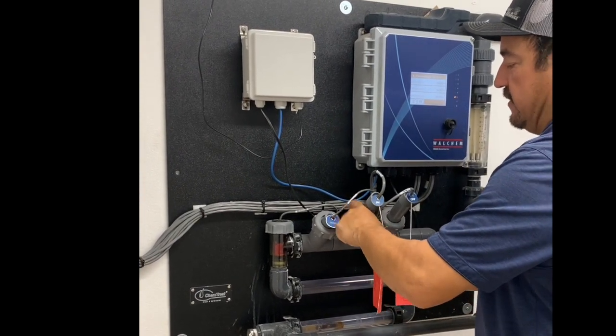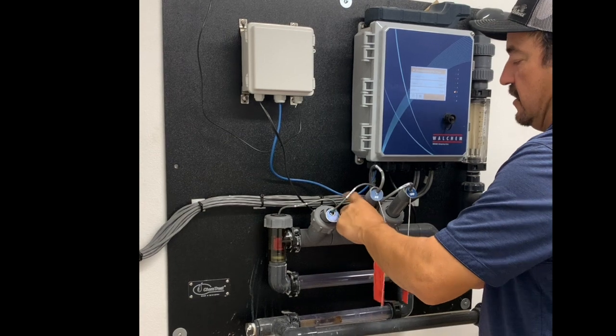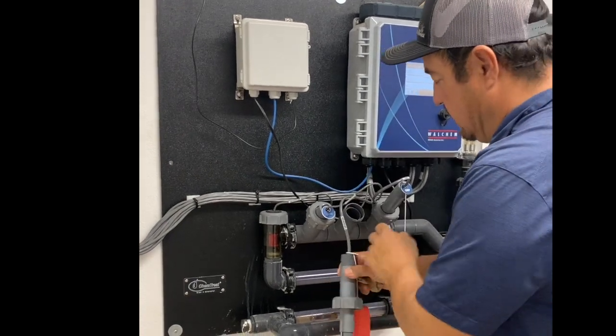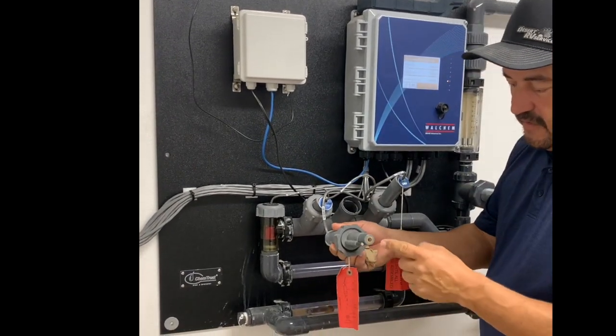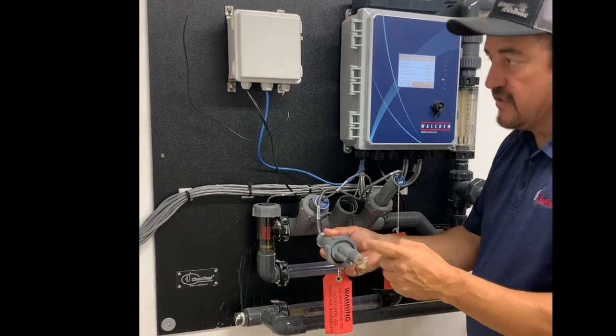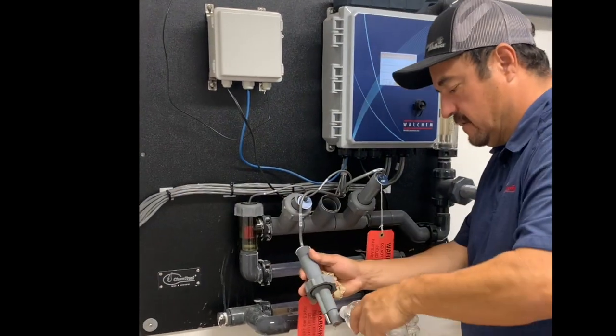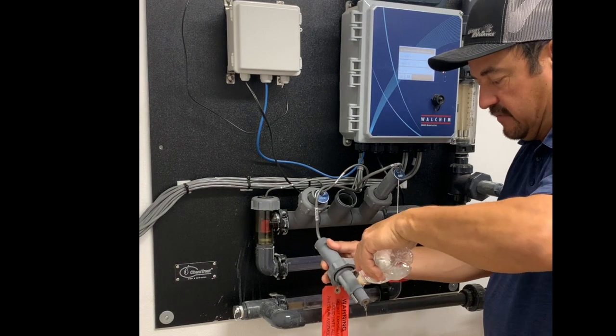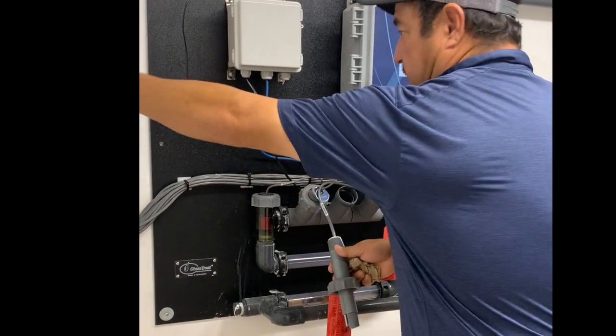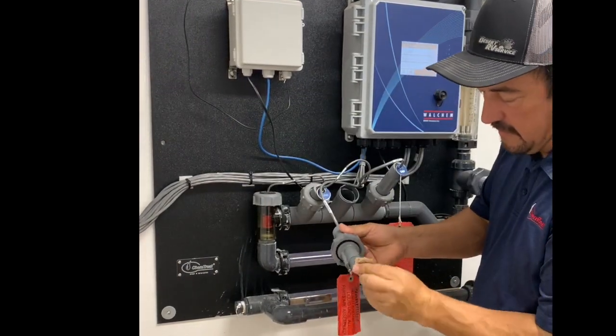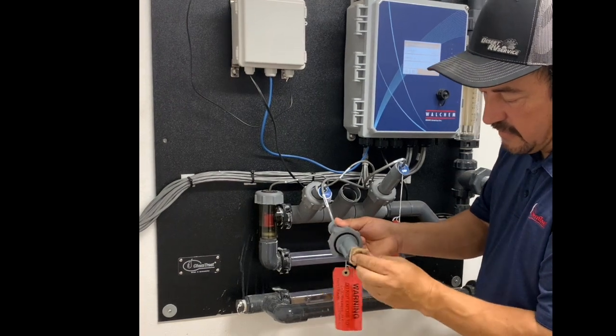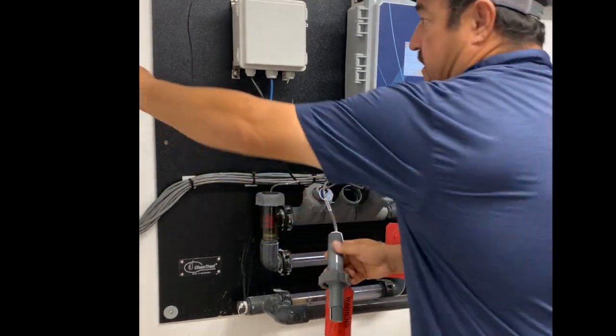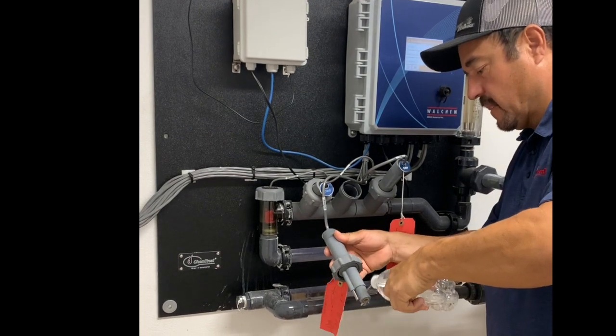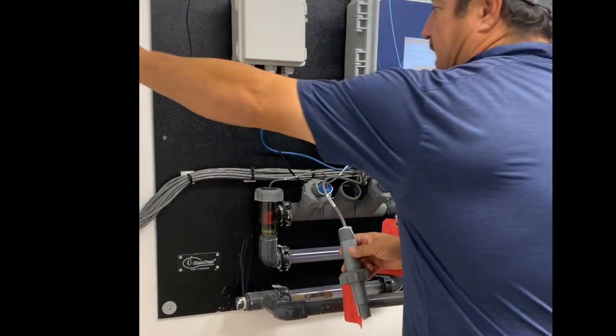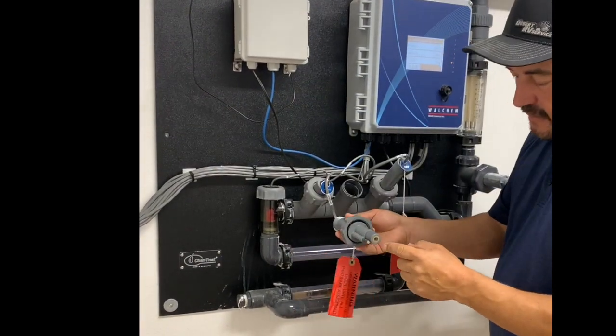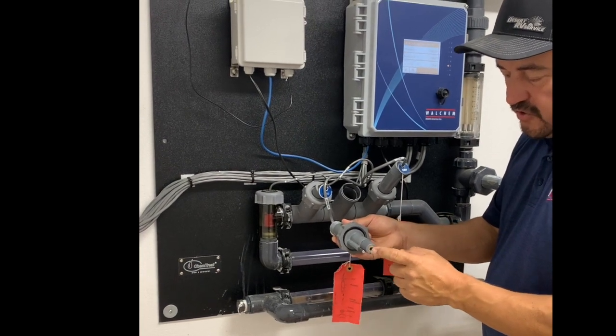The pH probe's a little different, as well as the ORP. Once again, make sure our O-ring's in there. You notice it has a glass on it. Same thing, rinse it off. Real light wipe. Clean off the probe. Very important is that the glass on here is very thin. So you don't want to use anything harsh to rub on it.